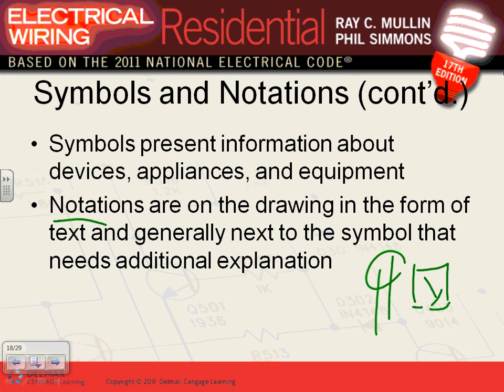So this is a symbol of a receptacle, right, a duplex like this, and the note right here will say, under my notes, receptacle to be installed or shall be installed 72 inches above, not feet, 72 inches above finished floor. So it seems they want them high up there for a plasma TV in residential, or whatever.